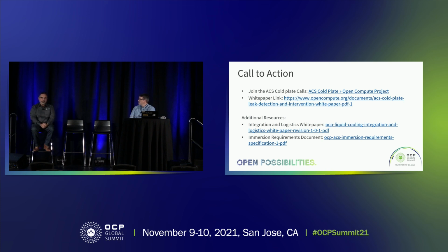In a lot of cold plate solutions, you'll notice that maybe 70% of the heat in the IT will be going into the fluid, and there still needs to be some air involved in that process potentially if you're doing a cold plate solution. So you have to consider that as you add manifolds, and multiple PDUs and whips that are powering those power systems can be quite large in diameter. There's a lot of work you have to do to understand that piece of it, but I think the connector sizes will change in scale, though they'll be limited.